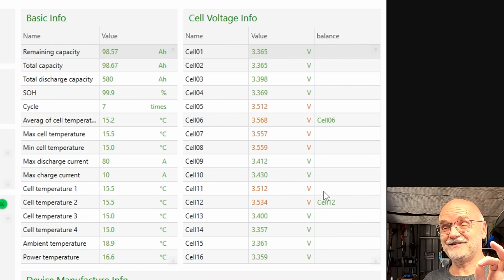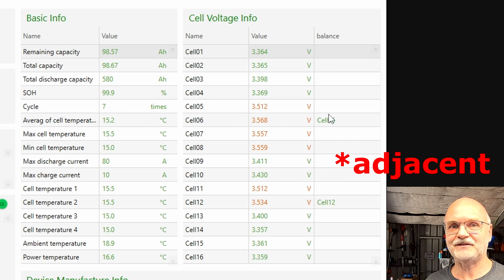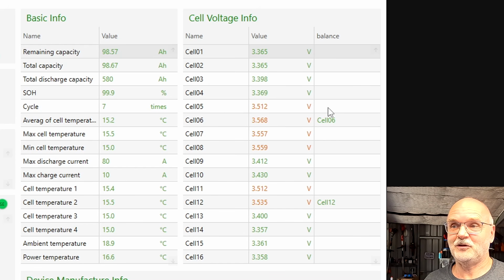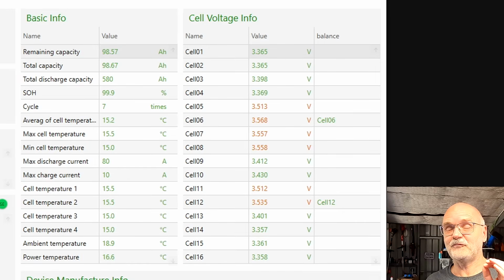I asked this question many times in our SEPLOS chat, and apparently this is per design - they're trying to avoid the balancer getting too hot, so they're not balancing adjacent cells. If cell number 6 is balancing, we cannot balance cell number 5 or cell number 7, due to a risk of overheating and a risk of a short. Just passing on what I've been told. If we go higher with our pack voltage, this is why I always see only battery numbers 3, 6, 9, and 12 balancing. None of the others - I've never seen any of the other battery cells balancing.